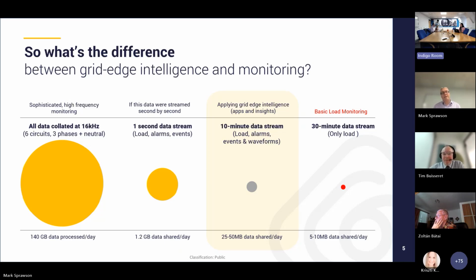The clever part of grid edge intelligence is not just to collect and process this data, but to turn it into something usable and actionable by the DSO. Instead, what's sent is a stream of load data, alarms, events, and key waveforms of incidents happening on the network, around 25 to 50 megabytes per day. That's only about 5 times more than smart meter data, but it's processed to be immediately actionable. That's the key thing about grid edge intelligence.